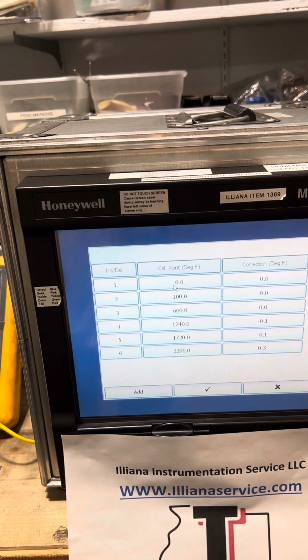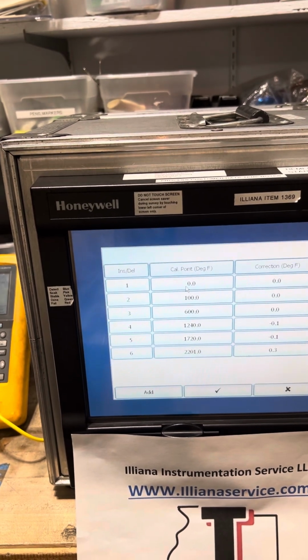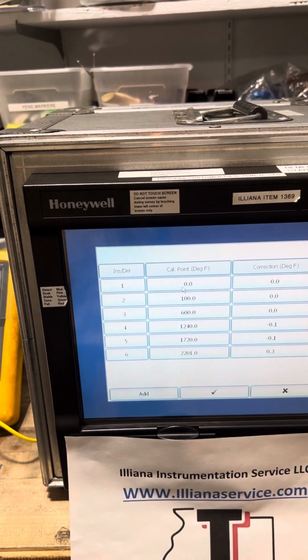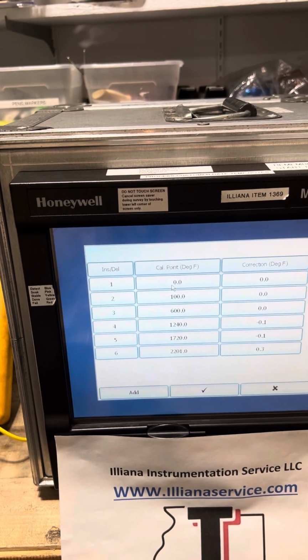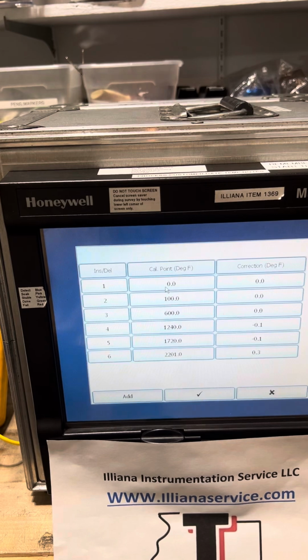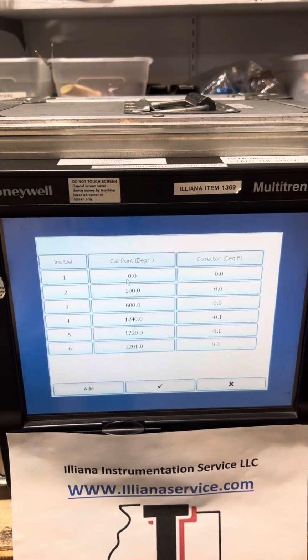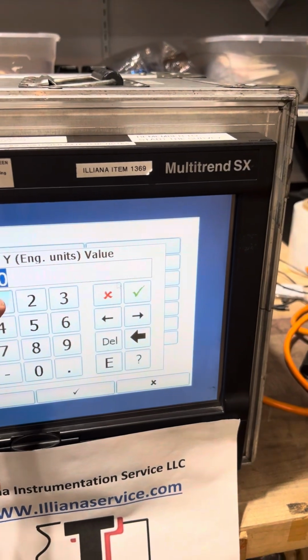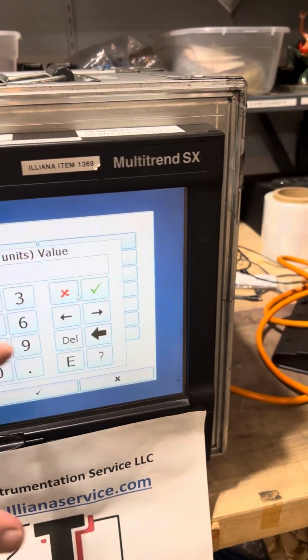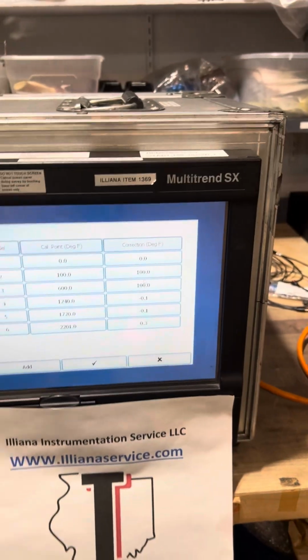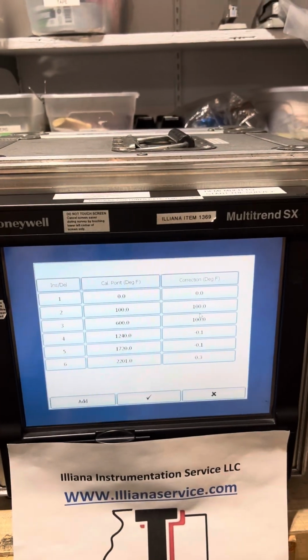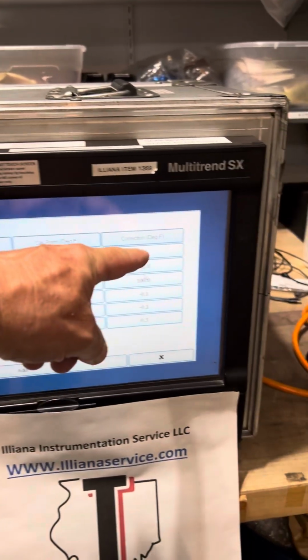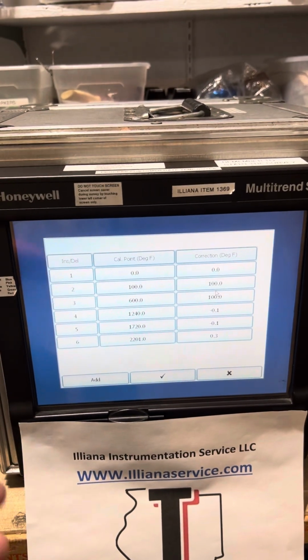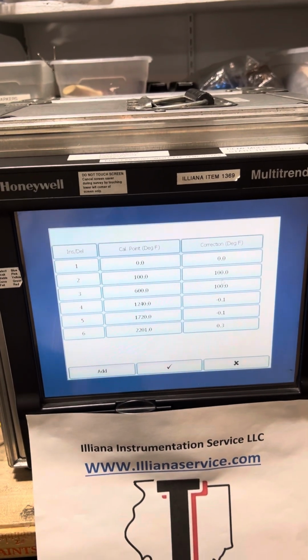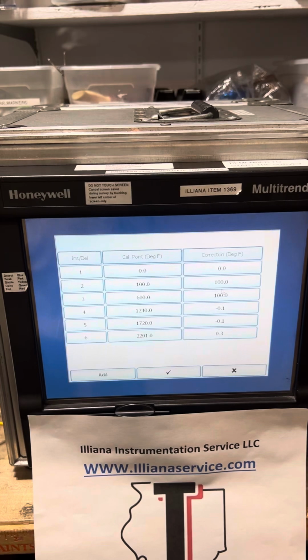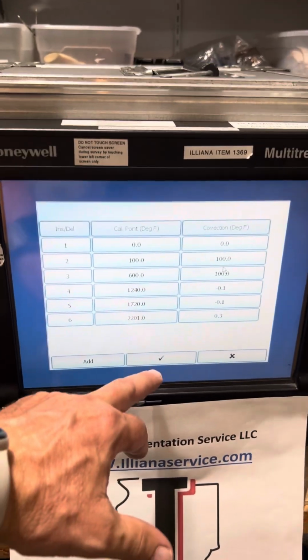So in my example right now, I'm going to put some values in there that are going to change the reading on the recorder. So at 100 degrees, I'm going to put in 100, and at 600 degrees, I'm going to put in 100. So basically now if I put in a value to the recorder of 0, it's going to add 0 and it should read close to a 0. When I get up to 100 degrees and I put that value in, the recorder is going to add 100 degrees as an offset, and you'll see that the recorder is going to read high.